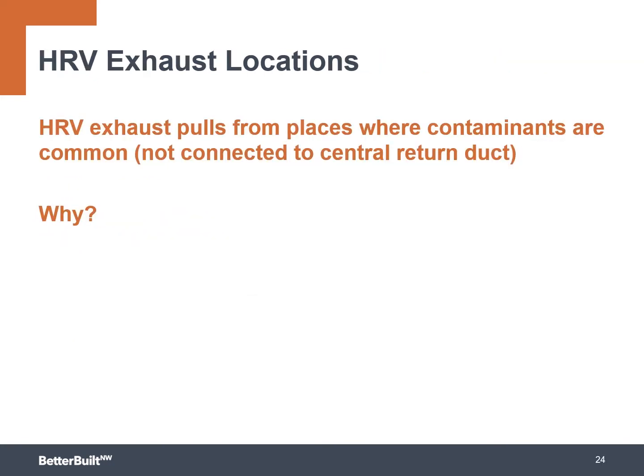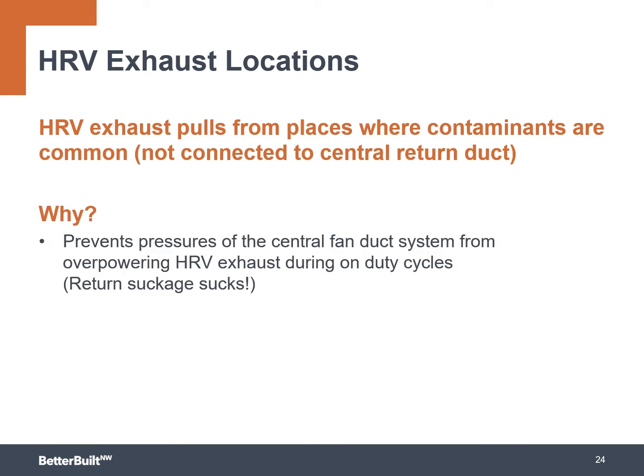Again, we cannot emphasize this enough. We really want to pull the exhaust from the places where the contaminants are common, as opposed to connecting it to a central return duct. Why? We want to prevent pressures of the central duct system from overpowering our HRV. That can actually happen when you connect an exhaust to the return side of your HRV.